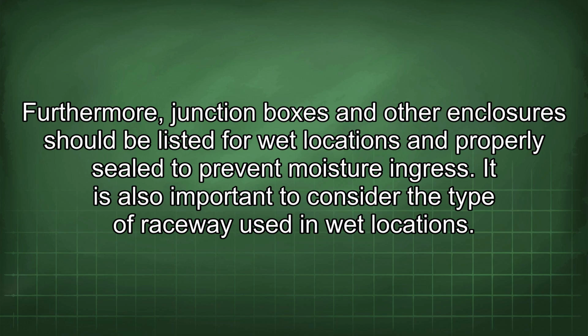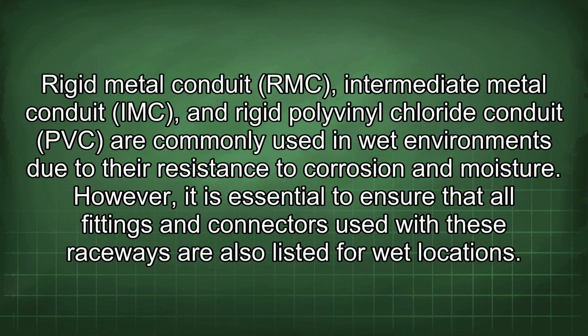It is also important to consider the type of raceway used in wet locations. Rigid metal conduit (RMC), intermediate metal conduit (IMC), and rigid polyvinyl chloride conduit (PVC) are commonly used in wet environments due to their resistance to corrosion and moisture. However, it is essential to ensure that all fittings and connectors used with these raceways are also listed for wet locations.